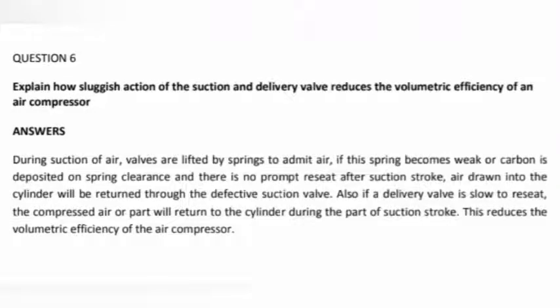Question 6. Explain how sluggish action of the suction and delivery valve reduces the volumetric efficiency of an air compressor. During suction of air, valves are lifted by springs to admit air. If the springs become weak due to high temperature or carbon is deposited on spring clearance, and there is no prompt reseat after suction stroke, air drawn into the cylinder will be returned through the defective suction valve.